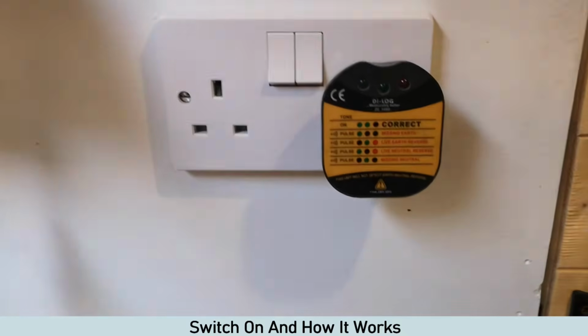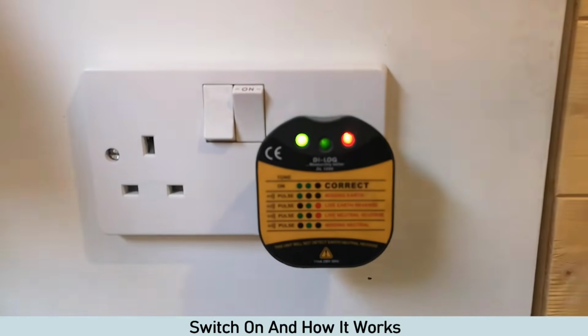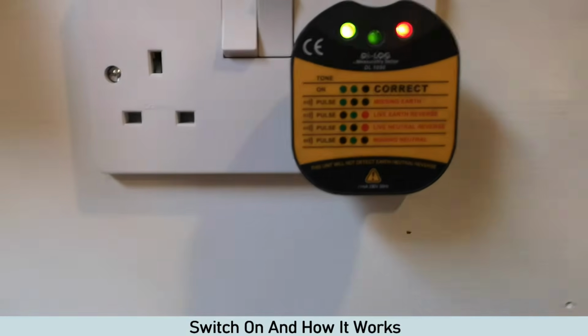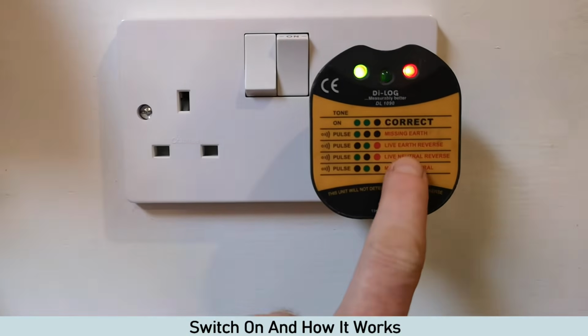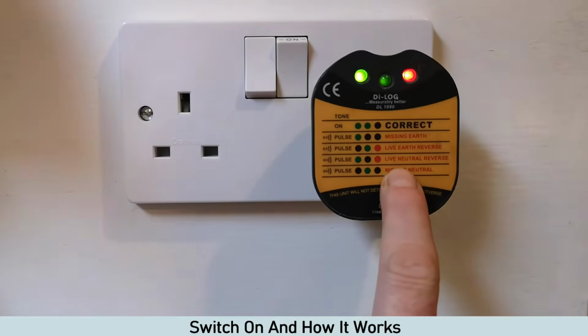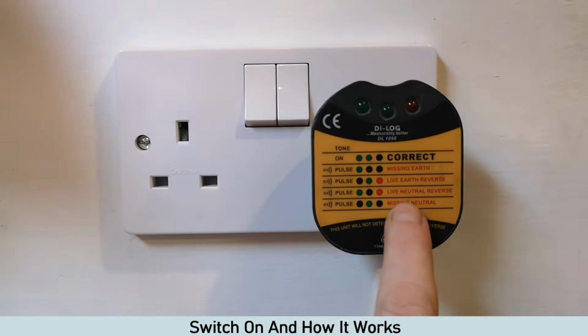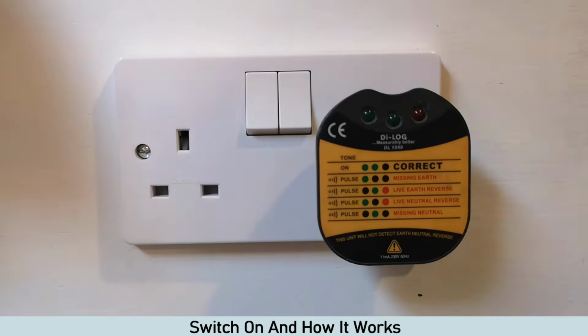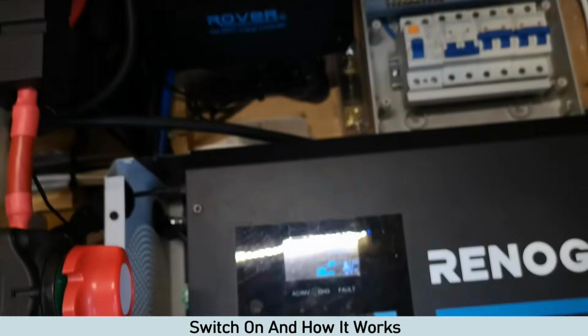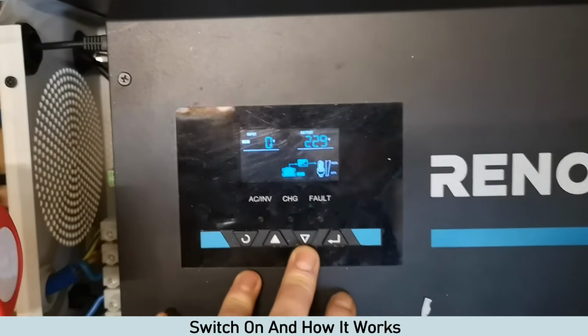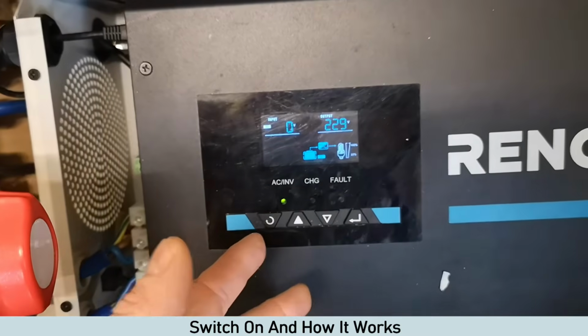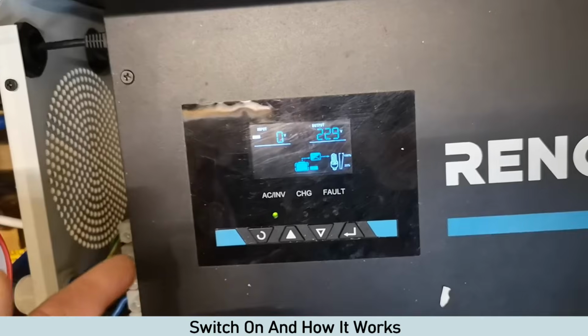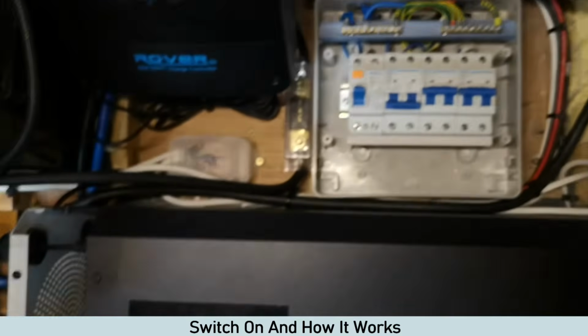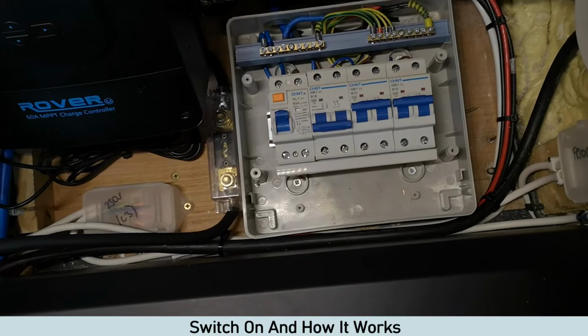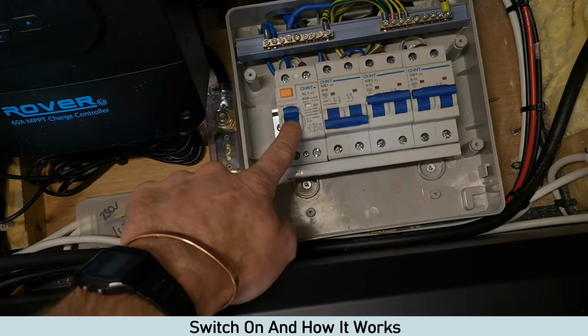Now what I'll do is the test button. Okay, so back at the socket, same scenario. We have a problem. What it is saying is live neutral reverse here. Obviously it's not live neutral reverse, because we've just done a test to prove that. Sorry, just turn it off. But that thinks there's a live and neutral reverse. Now the reason for that is, the power coming out of this inverter charger, even though it's pure sine wave, and people will think pure sine wave is the same as what comes out of your house. Technically it is, because you're getting 230 volts. But how this power is delivered is different to the power that we had before coming in, that I explained. Which is the reason why we're getting that reading, and I'll do some tests in a bit and show you the reason why this RCD is not actually working.